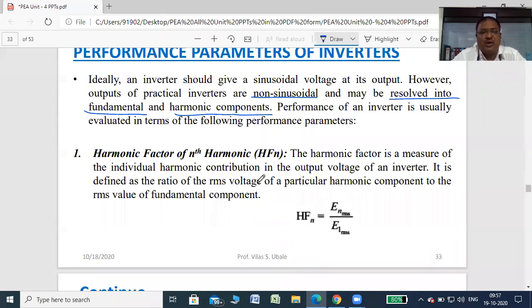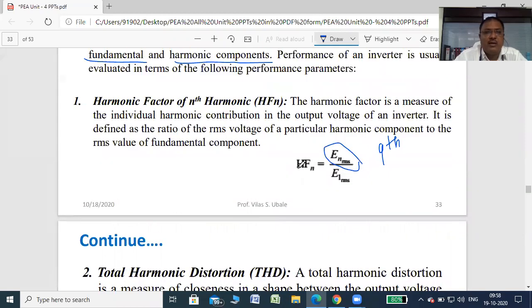It is defined as the ratio of the RMS voltage of a particular harmonic component to the RMS value of the fundamental component. Say it's the ninth harmonic component: the RMS voltage of this ninth harmonic divided by the RMS voltage of the fundamental component. So the harmonic factor of the nth harmonic is given as En(RMS) by E1(RMS). En is the voltage level of that nth harmonic component with respect to the amplitude of the fundamental component, and E1 is the RMS value of the fundamental component. This is called the harmonic factor of the nth harmonic.